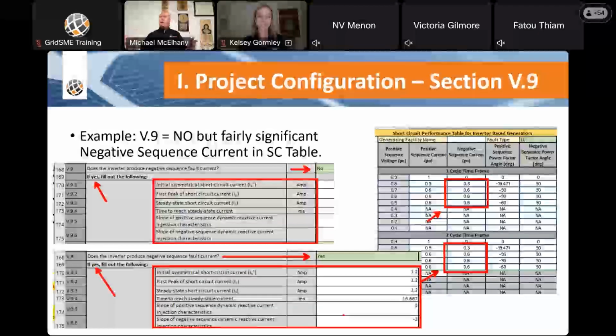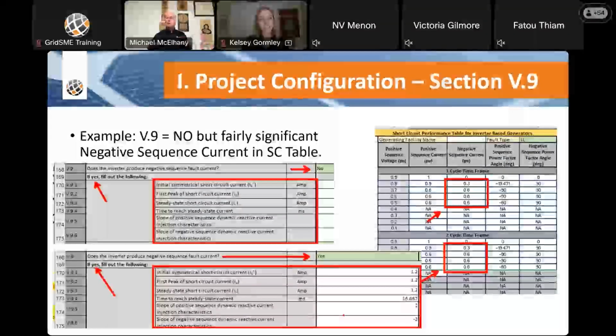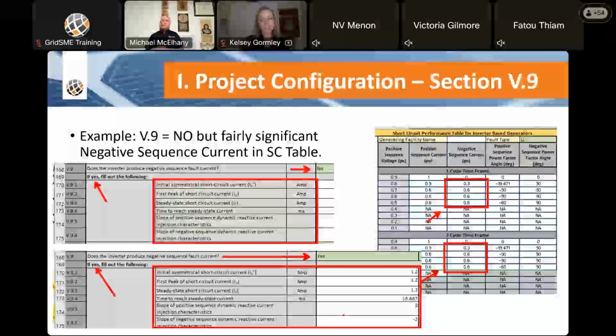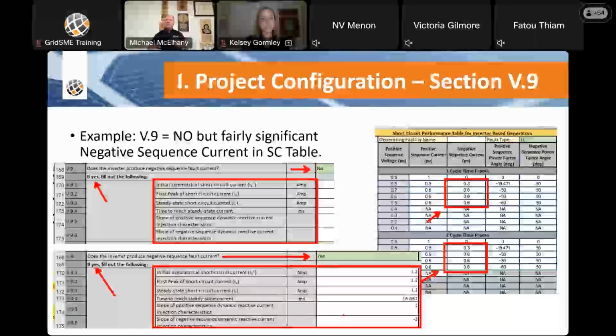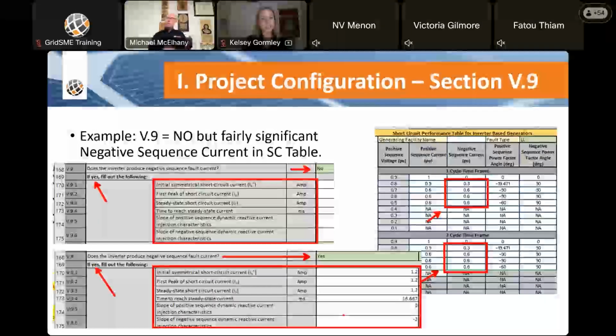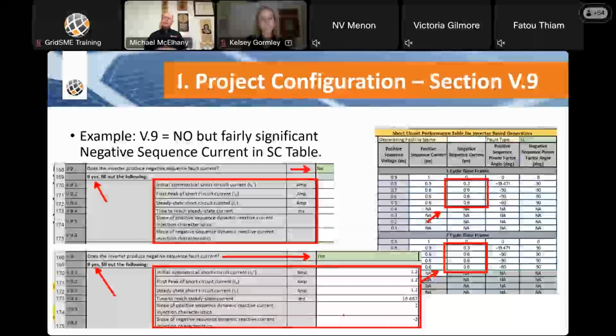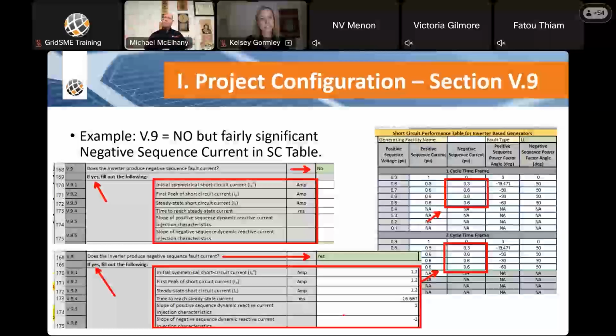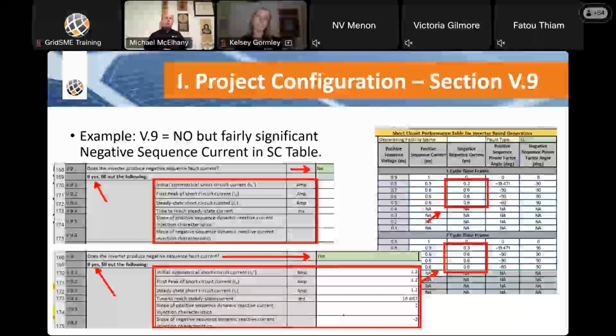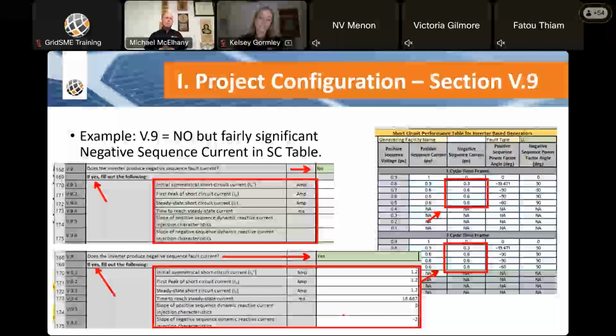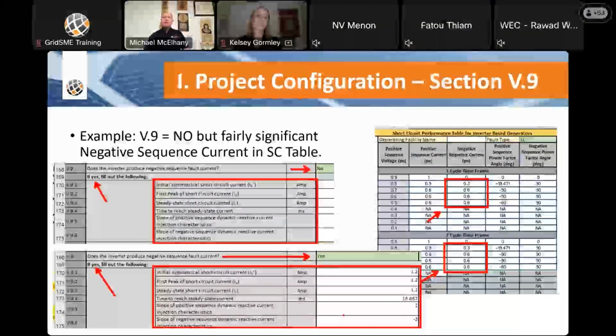So it's a big can of worms, but we've been working with the inverter manufacturers to get this down. We've been working with the California ISO. One thing to note: through our efforts, California ISO actually became aware that PG&E was starting to require negative sequence current being enabled in inverters, and yet CAISO has never studied it. So just something to be aware of, that there are additional nuances that we keep tracking with the inverter manufacturers, the clients, and PTOs and CAISO specifically.